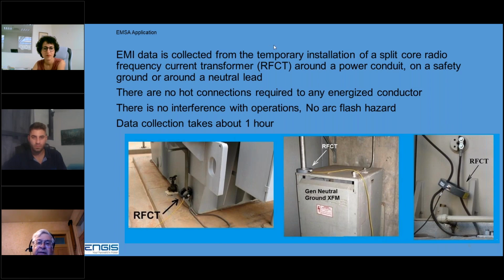Data is collected from the temporary installation of a split core radio frequency current transformer, RFCT. This is placed around a power conduit, a safety ground, or neutral. Here's the RFCT on the HO ground on a transformer. This goes up to the HO bushing. Grounding transformer on a small generator. This goes up to the neutral of the generator. And here's the safety ground on the side of a GE generator.